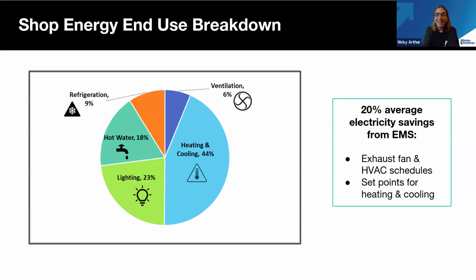More importantly, comparing stores where we've installed the system versus where we haven't, we're able to achieve an average of 20% electrical savings through the installation. That's been huge, and primarily I'd say that comes from being able to limit exhaust fan run times, and also having set points for heating and cooling, tightly setting those schedules for each store. So basically we're only conditioning the air when we need it.